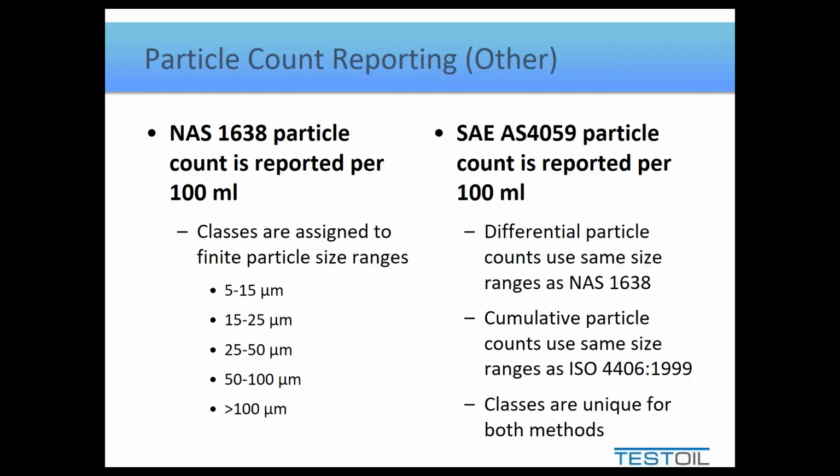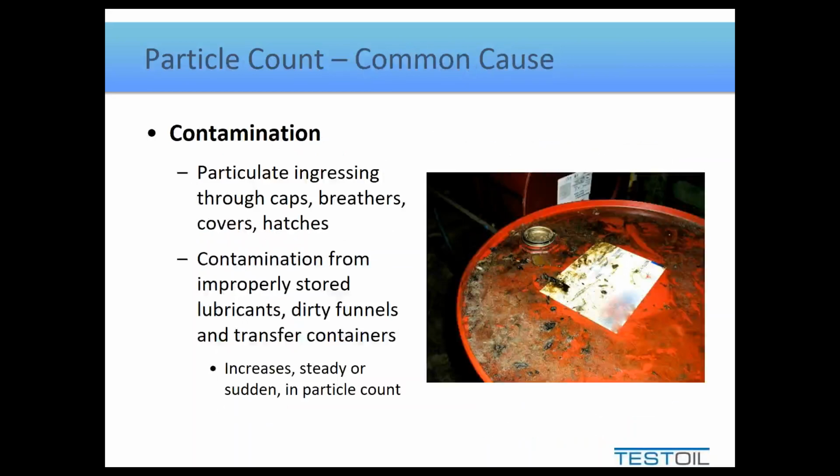So saying all that, we're talking about how the numbers are reported. We haven't talked about how to interpret them. What causes your particle count to go up most commonly? Contamination, obviously. You've got particles in your oil. So how do particles get in? Basically, any way they can.